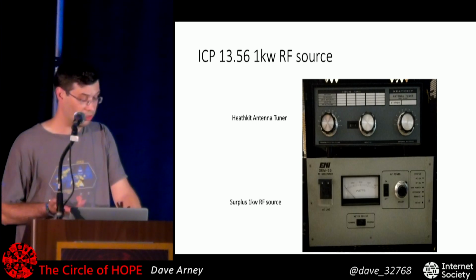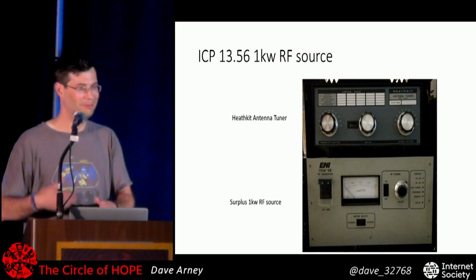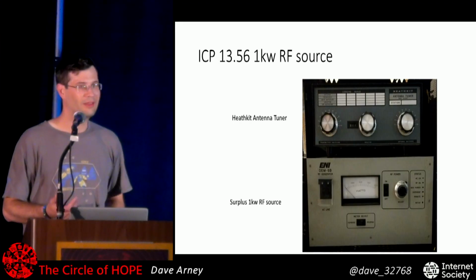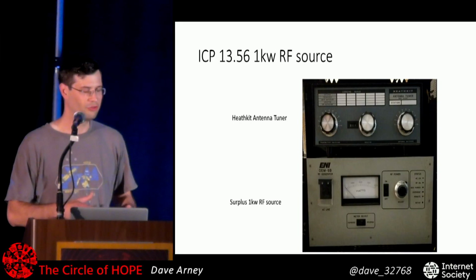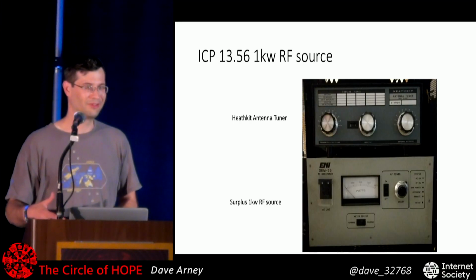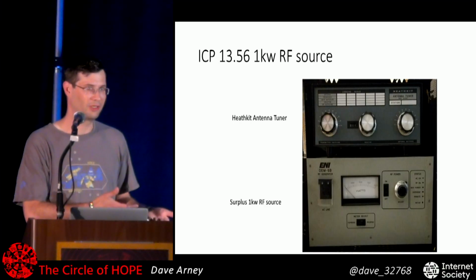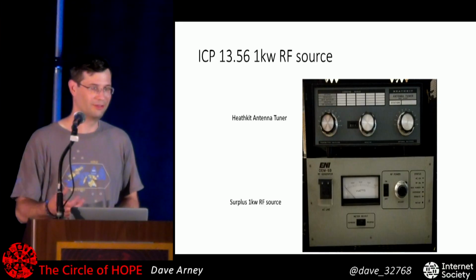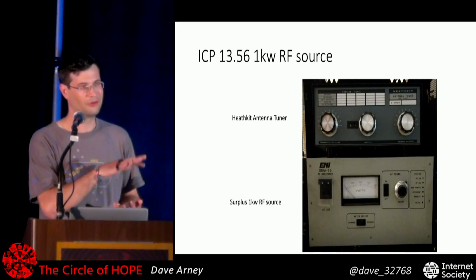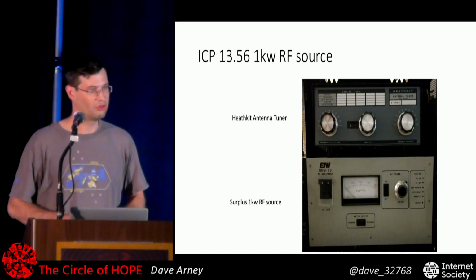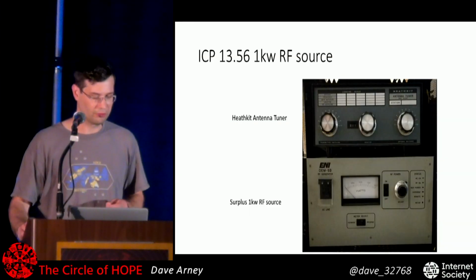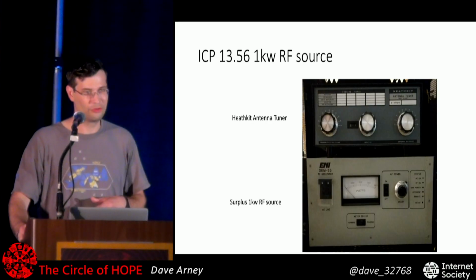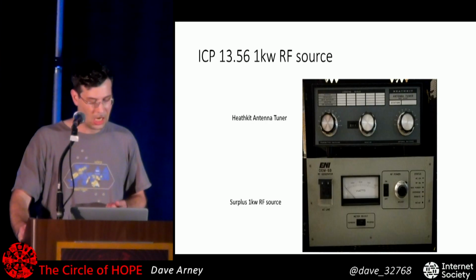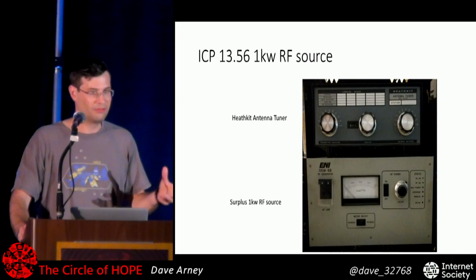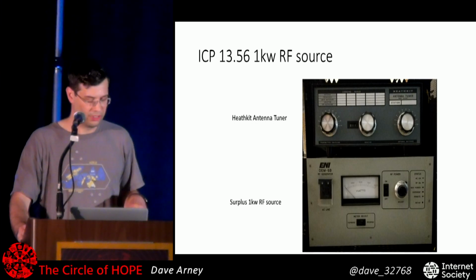This thing is still water-cooled, so you have to have a water pump and other supporting equipment. Another recurring theme is that there's a lot of infrastructure around getting this running. Just to get the valves working, you need an air compressor, regulators, and solenoid valves to turn on and off the right air lines at the right time. Similarly, to get the RF source to turn on, there has to be water running through it - it has a flow sensor and will shut off if there's not sufficient water. It also has an interlock where if it's not connected to a control system, it won't turn on.